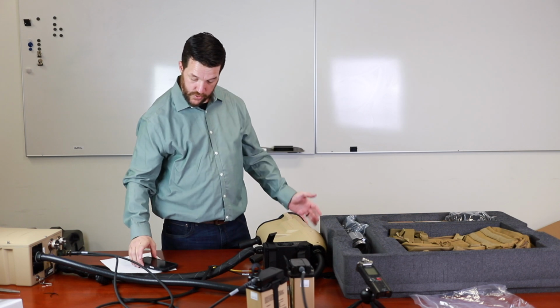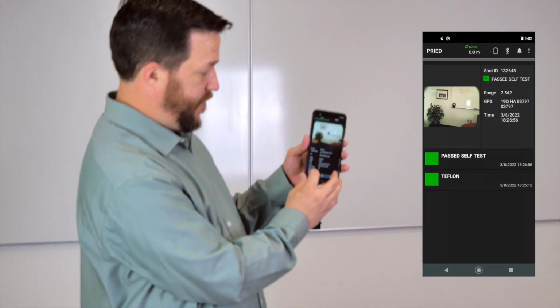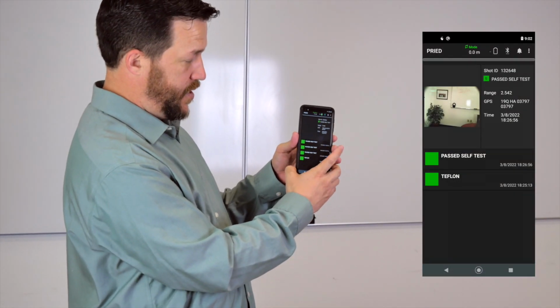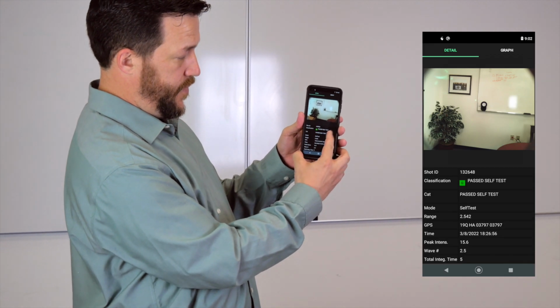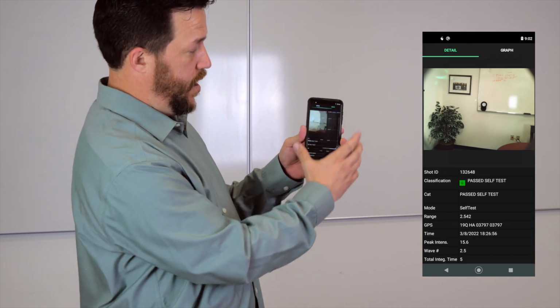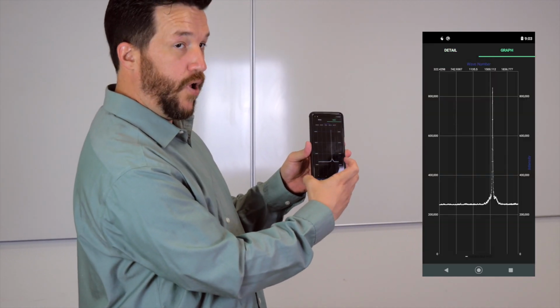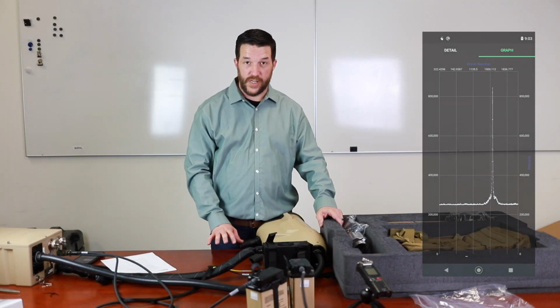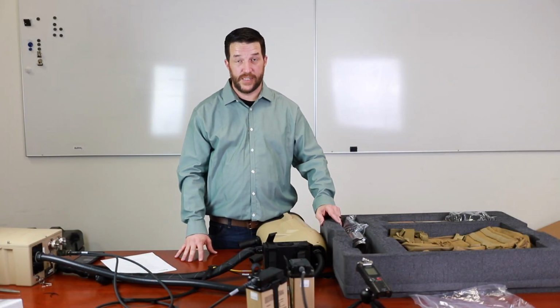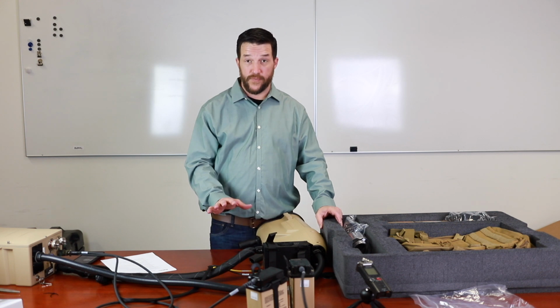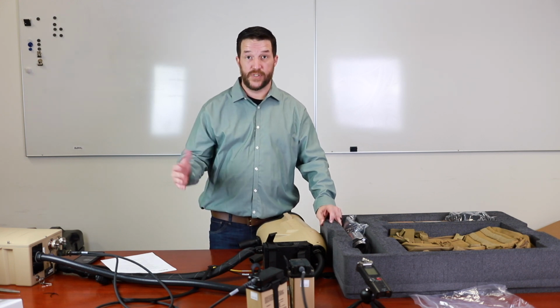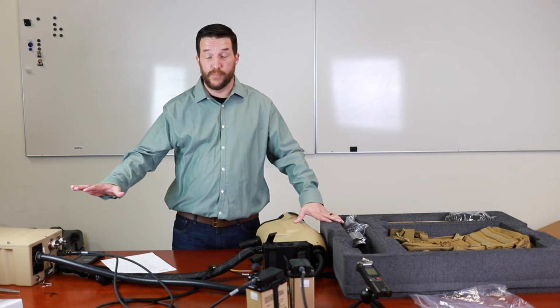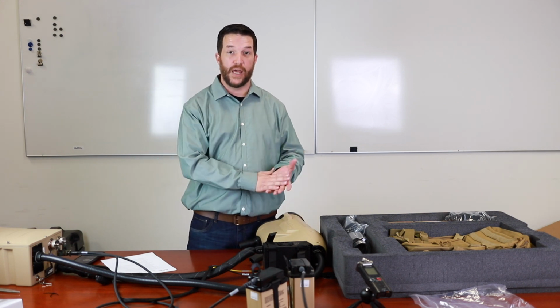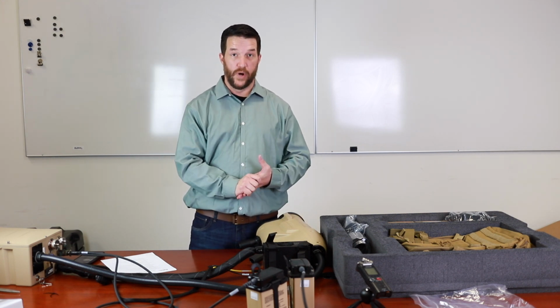We can come back to our droid and see that we have now got a pass self-test. And here's our information. Nice, beautiful oxygen peak. So after you receive a passing self-test and a passing Teflon test, we have validated our system's performance levels.